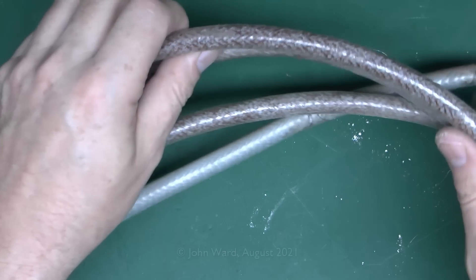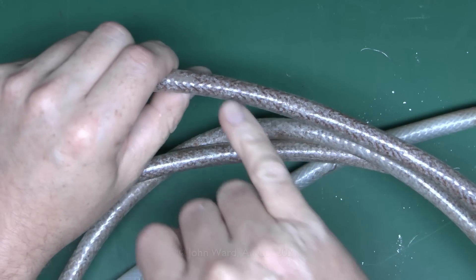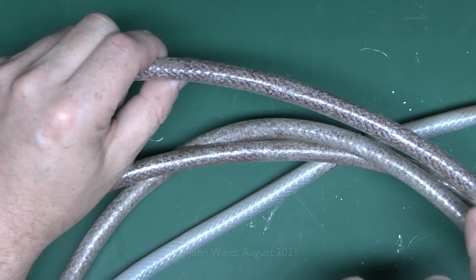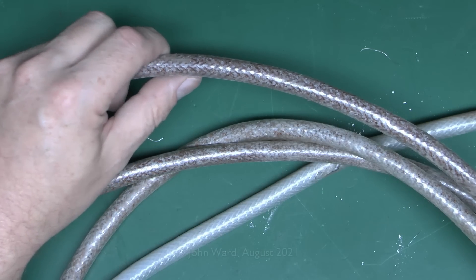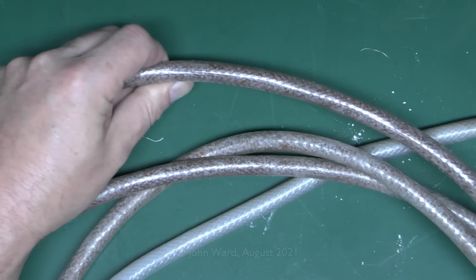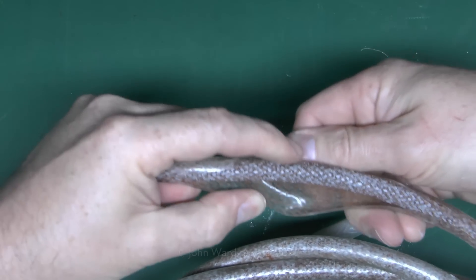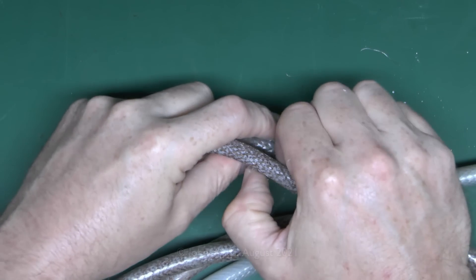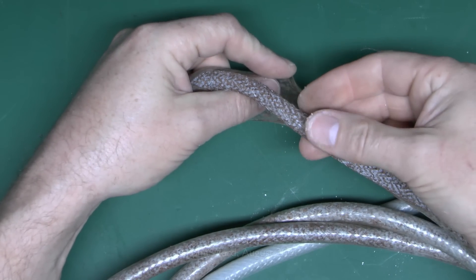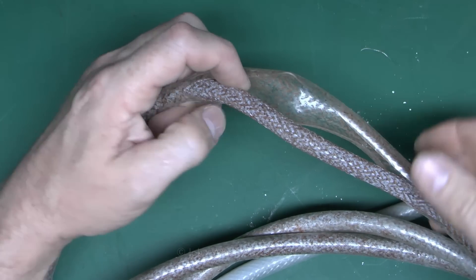If we look further along this cable, we can see the next problem. This was actually underground, and as you can see, the outer covering is still nice and transparent, but inside it's no longer a shiny silver. The reason for this is due to corrosion. So if we just slash a piece open, we can see inside this is just a horrible corroded shambles. So all brown and disgusting, and all that colouring is just transferred over to the outer covering.